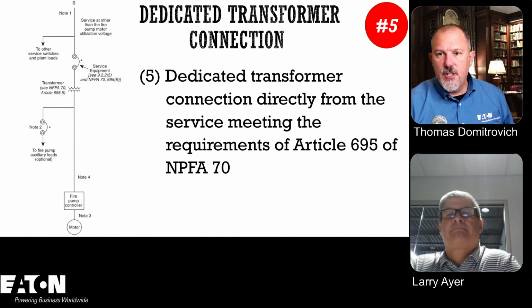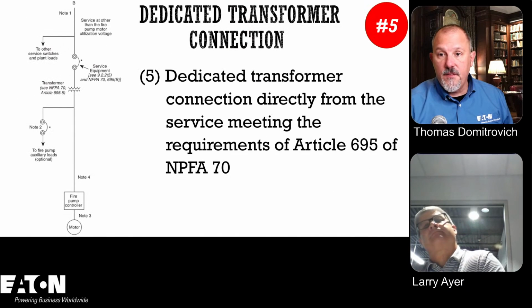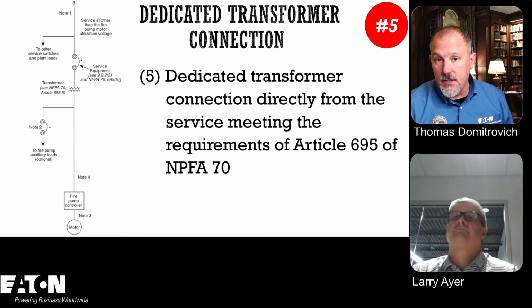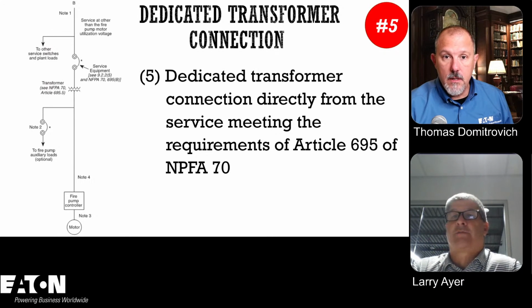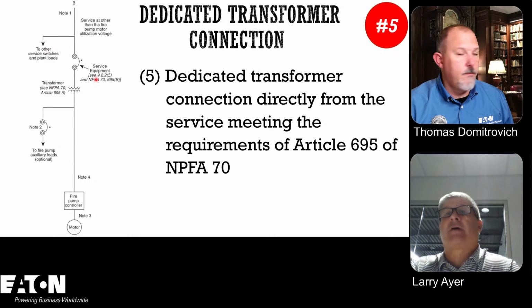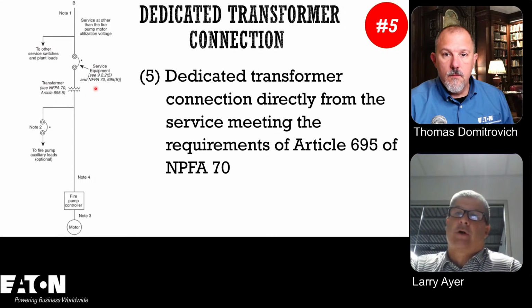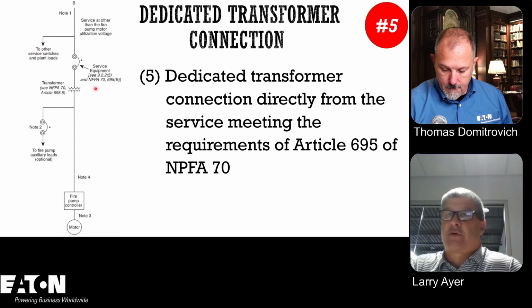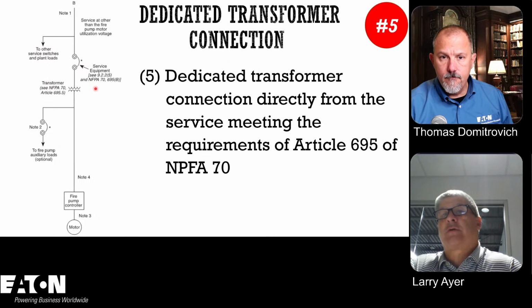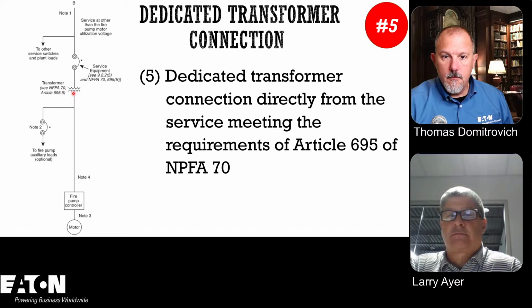Number 5 is your dedicated transformer connection directly from the service. We already talked a little bit about this one, right? Right. So, if you do have a different voltage coming in than your fire pump, you'll have your main service disconnect right there. Then you'll have your transformer, but you do not put any secondary overcurrent protection from that transformer over to your fire pump controller. Right.